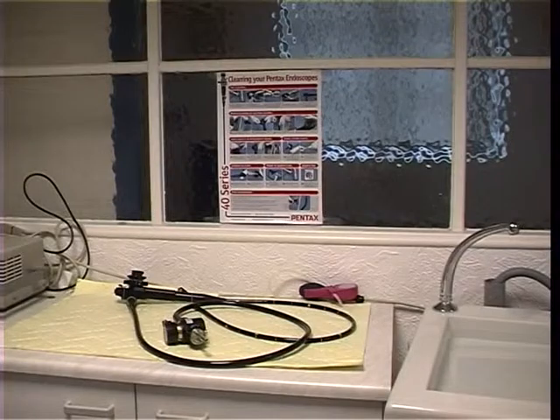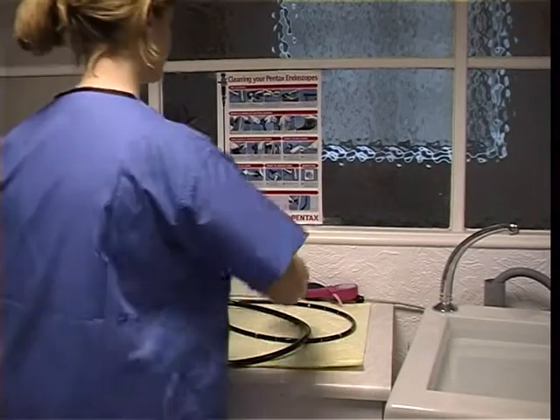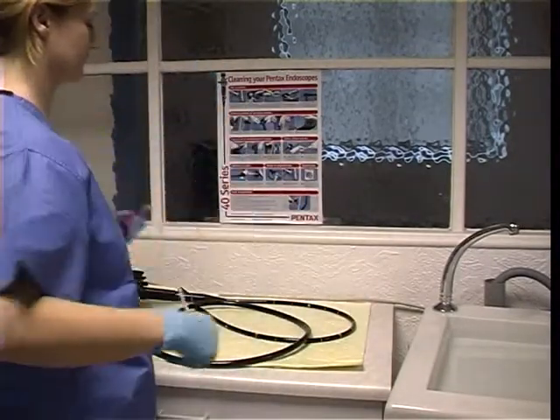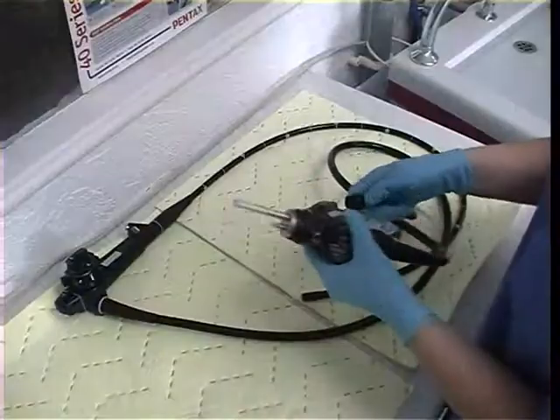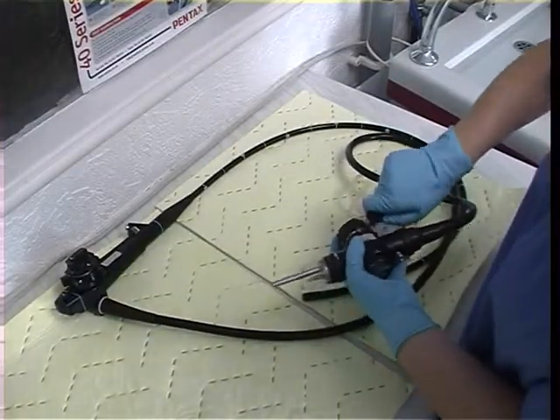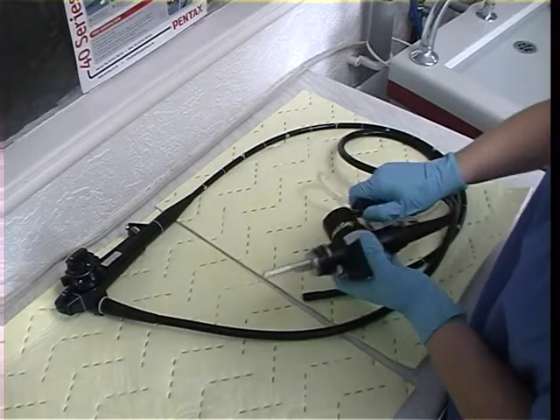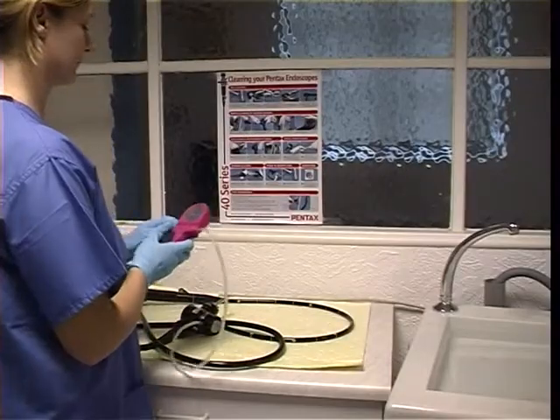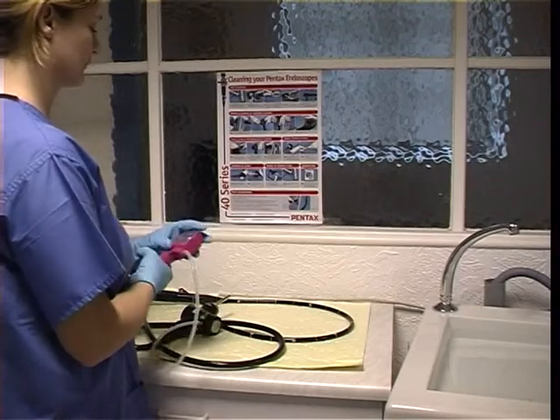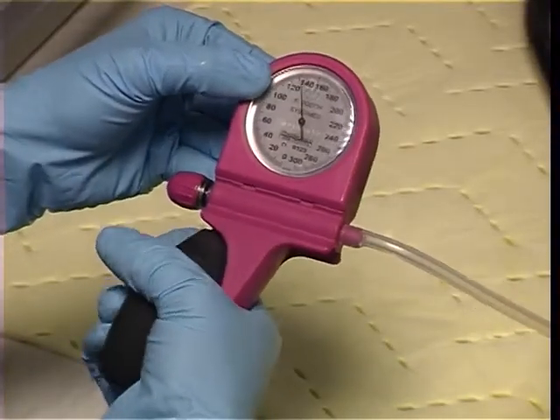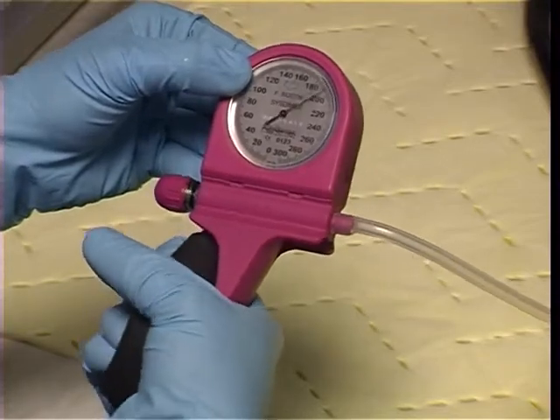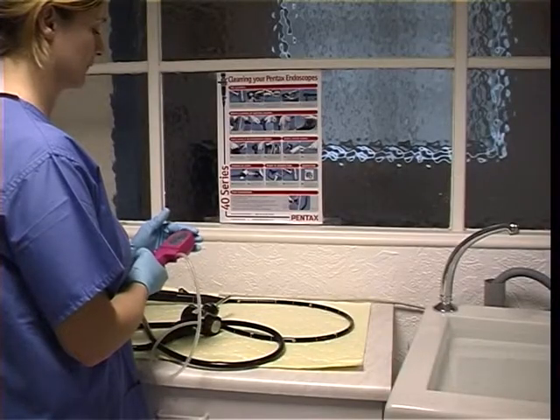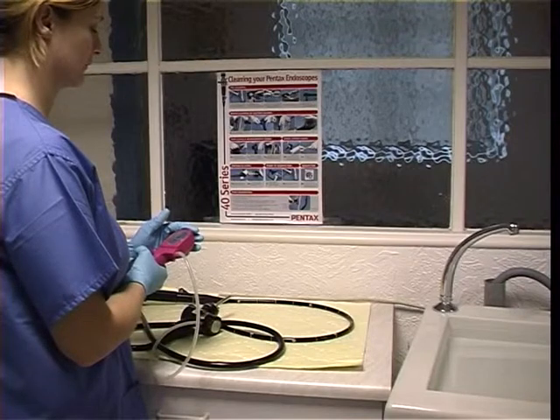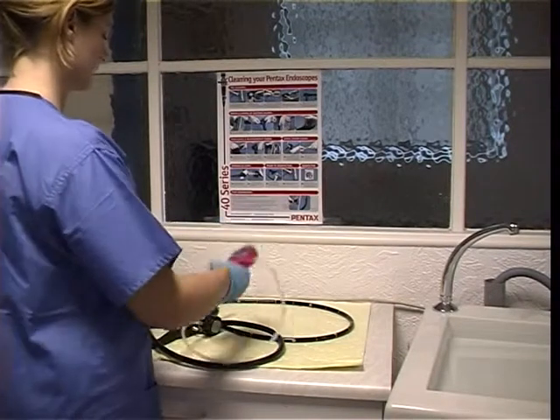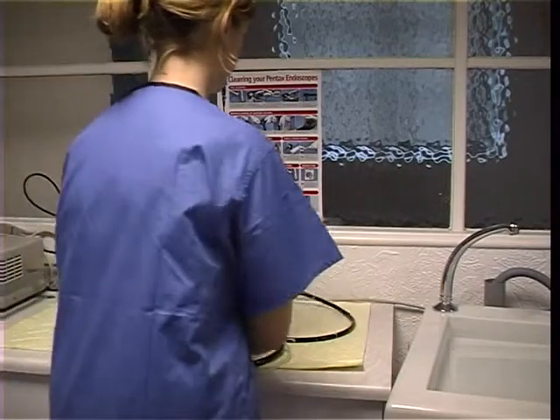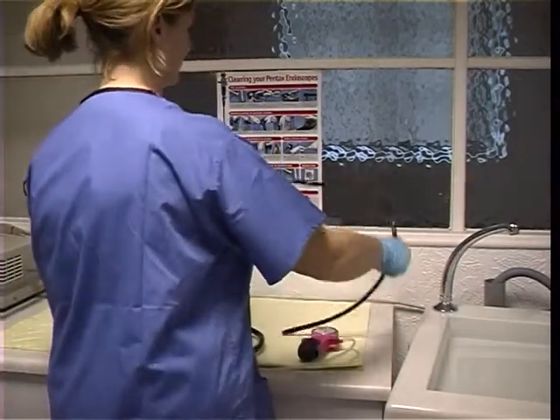You must wear your department or trust-recommended personal protective equipment to carry out this procedure. Ensure that your leak tester and the leak test connection are dry. This includes the internal part of the connection itself. Attach your leak tester to the endoscope. Inflate to the pressure indicated on the leak tester or as per the manufacturer's advised level and stabilize. Then observe the gauge for a drop in pressure. If a sudden substantial pressure loss is observed, do not immerse in water. Discontinue the test and organize to send the endoscope for repair.